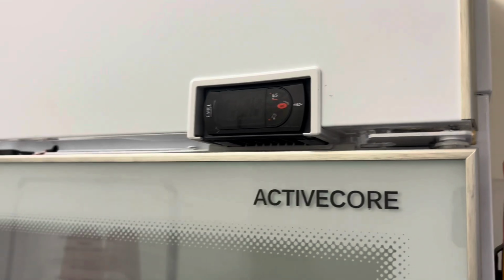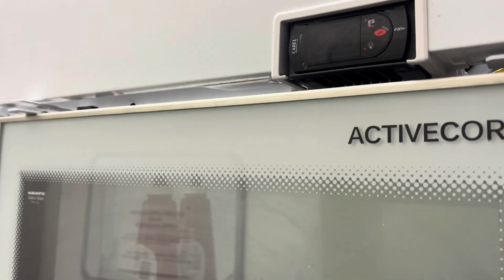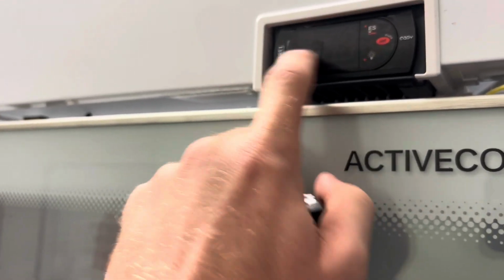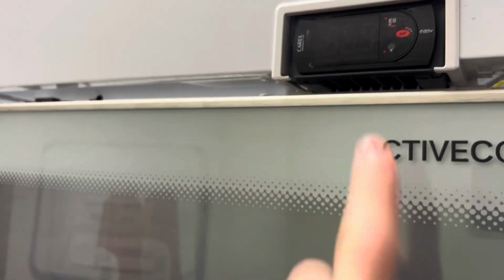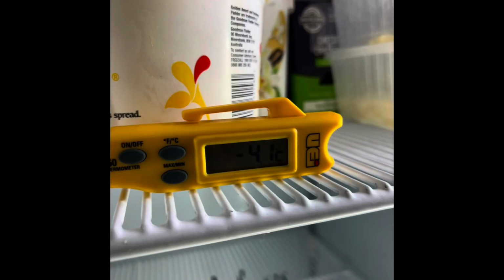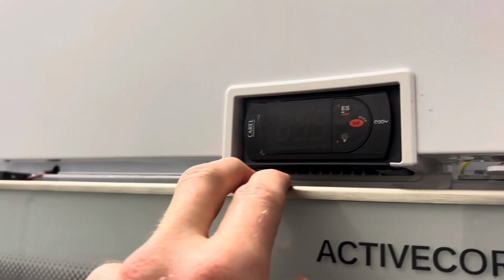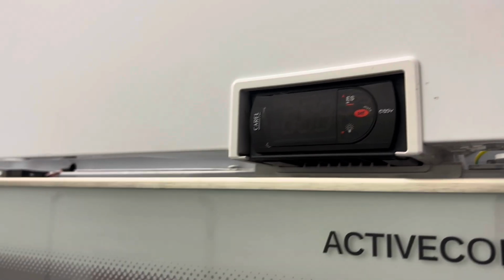Basically what was happening was the compressor wasn't cutting out when set point was reached. I'll put up a photo, but it was freezing all of the products in there. The relay inside the controller here, you can see, so I'll show you what I did to test that.